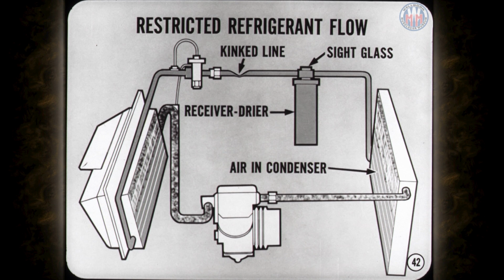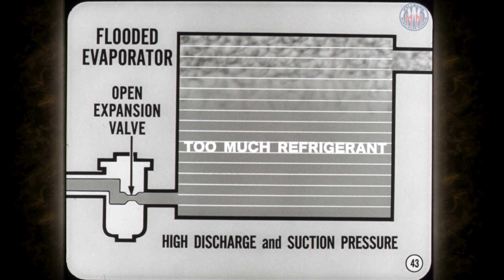Restricted refrigerant flow can be caused by a kinked line or by air trapped in the condenser. Either condition will build up the discharge pressure, but air also causes foam to appear in the sight glass on the receiver dryer. A flooded evaporator is usually caused by an open expansion valve, but too much refrigerant in the system can also cause flooding, even when the valve works properly. Both conditions cause high discharge pressure right along with high suction pressure.